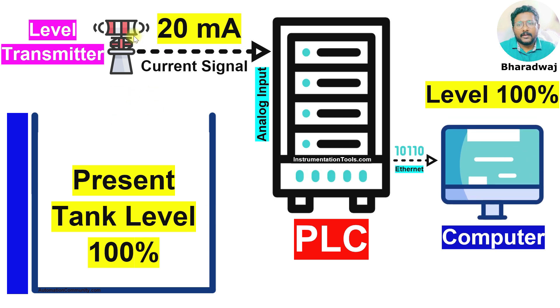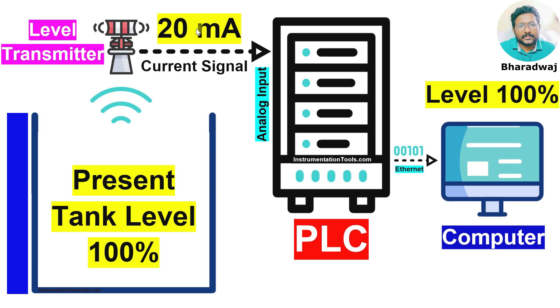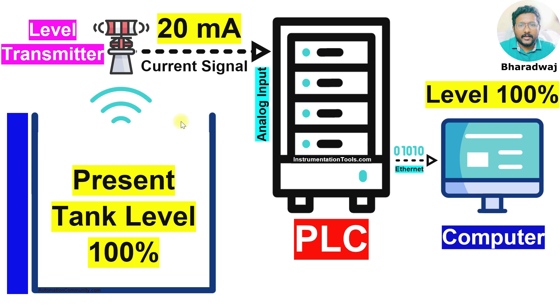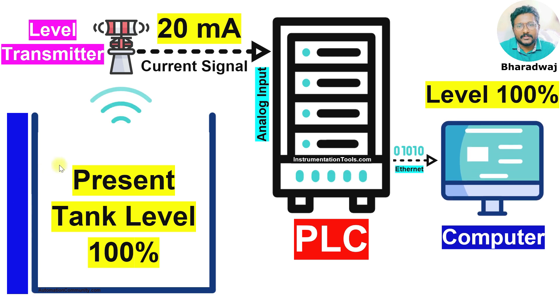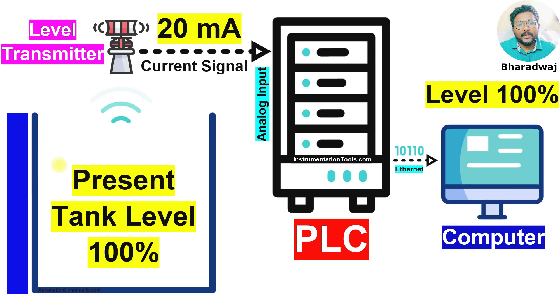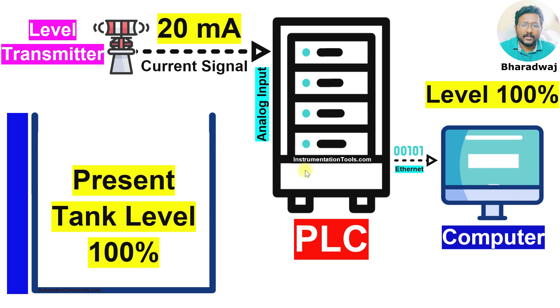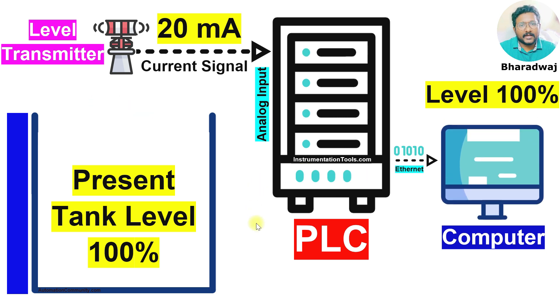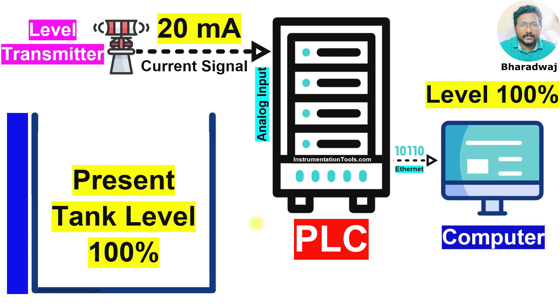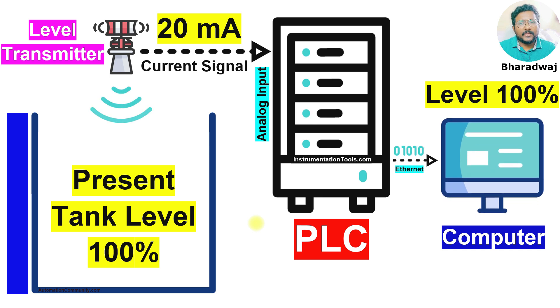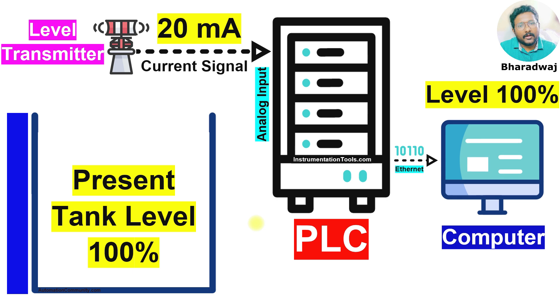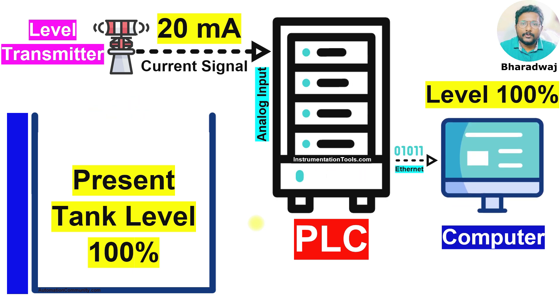At 0%, the transmitter sends 4 mA — that is the zero scale — and at 100%, the transmitter sends 20 mA to the PLC, which is the full scale value. In percentage terms: 0% to 100%, and in current terms: 4 mA to 20 mA. This is how the transmitter sends the current signal and the PLC calculates the equivalent process parameter value. This concept is the same for every instrument which provides an analog input to a PLC, DCS, or any controller based on 4 to 20 mA.